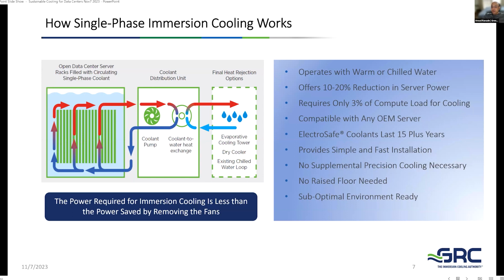So effectively speaking, for our tropical climate, a best-in-class PUE is 1.6. What it means is, if you have a 1 megawatt data center, its power consumption will be 1.6 megawatts. Comparatively, if I design a liquid immersion cooling data center, I can get you a PUE of 1.1, which means for the same 1 megawatt data center, I will actually consume 1.1 megawatts. Now bring into the picture the fact that 15% energy is already reduced because of the fan removal. So that 1 megawatt actually becomes an 850 kilowatt data center. So your overall data center consumption reduces by almost 50%, 600 to 650 kilowatts is reduced. And so there are tremendous opportunities to save in terms of energy, which adds to the company's sustainability goals.